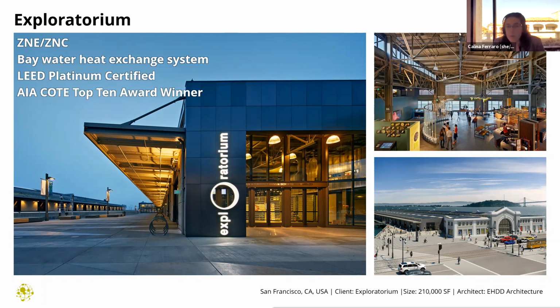And we have a displacement ventilation system. So when we are providing mechanical ventilation, we supply that air down low, we let it find the heat sources, and then as that heat warms the air, that warm air rises up away from the space. So that actually gives us really good air quality in the space because it's just passing through the occupied zone once, right? That displacement supplies low, mingles around with people, and then lifts itself up with the heat. So we get both good efficiency and also very good air quality.